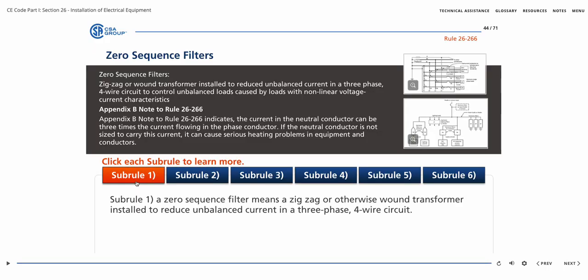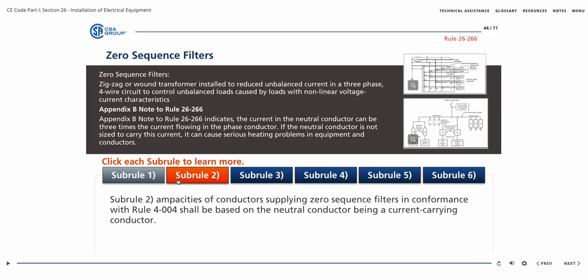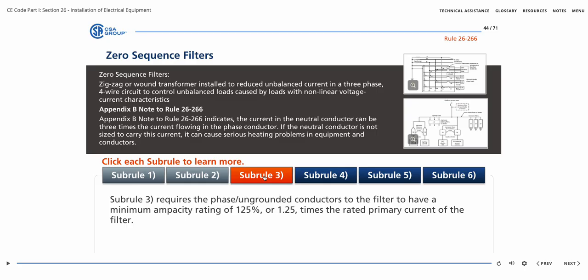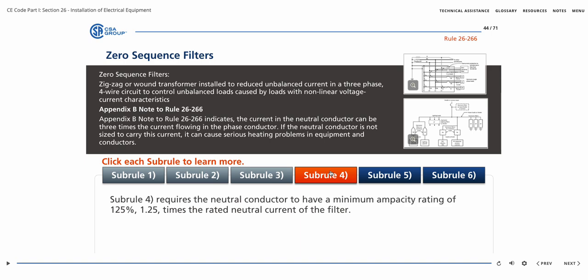Sub-Rule 1. A zero-sequence filter means a zigzag or otherwise wound transformer installed to reduce unbalanced current in a three-phase, four-wire circuit. Sub-Rule 2. Ampacities of conductors supplying zero-sequence filters, in conformance with Rule 4-004, shall be based on the neutral conductor being a current-carrying conductor. Sub-Rule 3 requires the phase/ungrounded conductors to the filter to have a minimum ampacity rating of 125%, or 1.25 times the rated primary current of the filter. Sub-Rule 4 requires the neutral conductor to have a minimum ampacity rating of 125%, 1.25 times the rated neutral current of the filter.